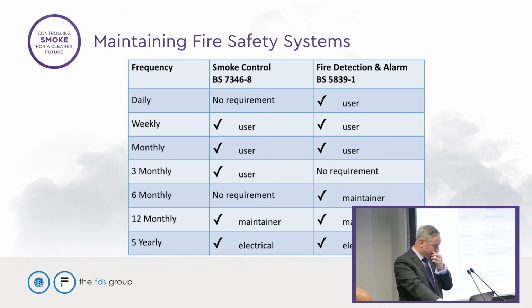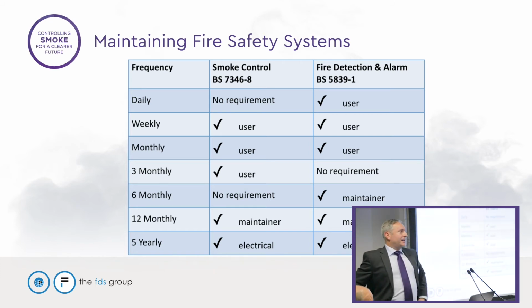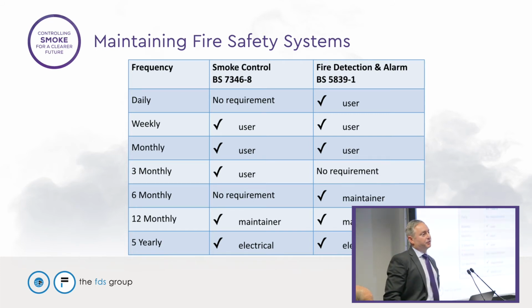And then at 12 monthly, we get into a comprehensive service where we're now checking 100% of the system, opening up all the panels and checking the wiring, the cause and effect, and all the devices are working correctly. And then at 5 yearly, we're doing electrical testing, and that's not anything that the smoke control or fire alarm company would do. It's something that you would get an electrical company to do. And we're not talking about the loop for detectors, we're talking about electrical safety, the provision of low voltage power to your panels or your 3-phase automatic transfer switches.